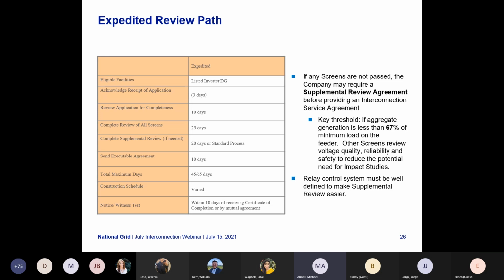Once assigned to a screener, there's 25 business days to proceed with all the screening and to determine if it needs supplemental review or it can be given an ISA. If screens are not passed, the company may require a supplemental review agreement before providing an interconnection service agreement. The key threshold is if the aggregate generation is less than 67% of the minimum load on the feeder. Other screens review voltage quality, reliability, and safety to reduce the potential need for impact studies. The relay control system must be well defined to make supplemental review easier.